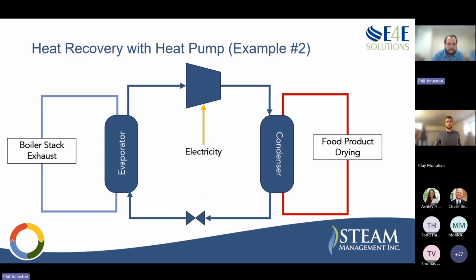So I've got one more example. Back to the same diagram here. On the heat source side, we have boiler stack exhaust. If you're not too familiar with a boiler, I'll briefly describe the process. It takes in combustion air and mixes it with natural gas, fires it, and uses that heat to turn water into steam. Every boiler, though, after that combustion process is done, has an exhaust stack where that hot air is dissipated into the atmosphere. What we like to do is recover as much of that heat from the boiler stack as possible and use it elsewhere in the facility. And heat pumps are a great way to do that.